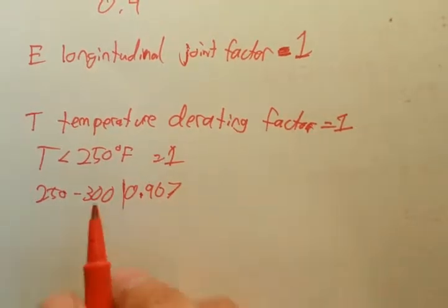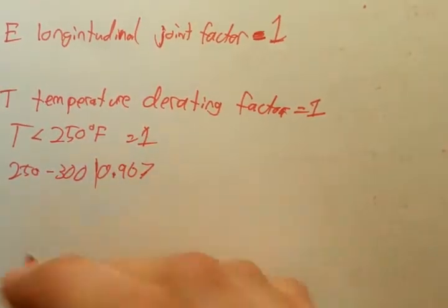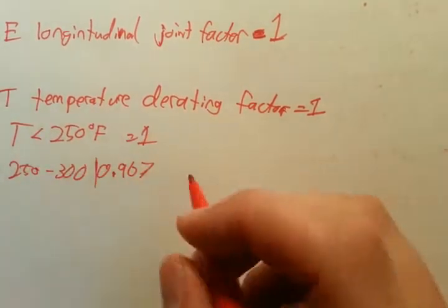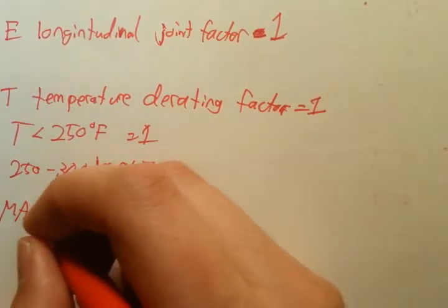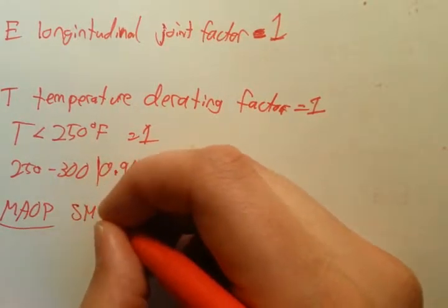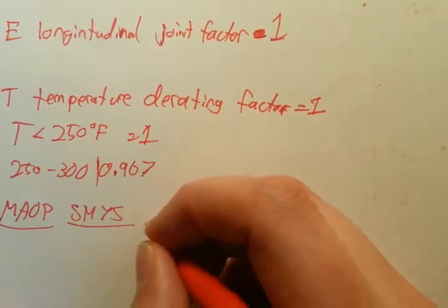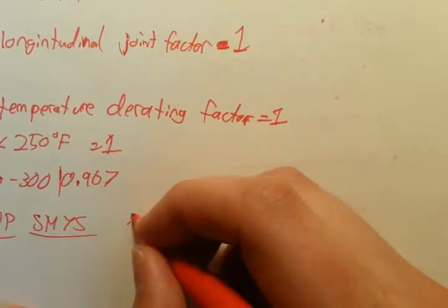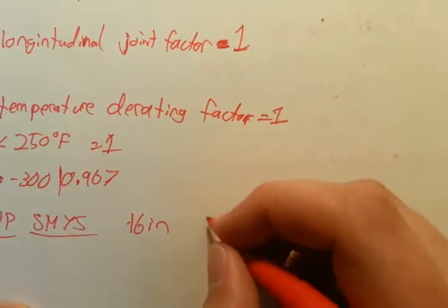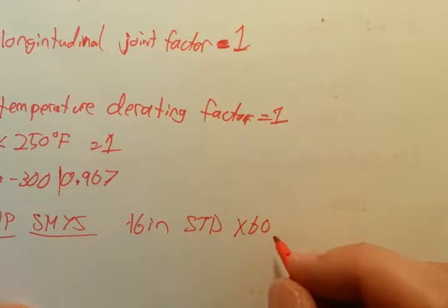Those are your three different design factors. We're going to do an example really quick. Let's say we want to find the MAOP and the yield pressure of a 16 inch pipe, standard wall, X60, and we'll say it's in a class 3 location.